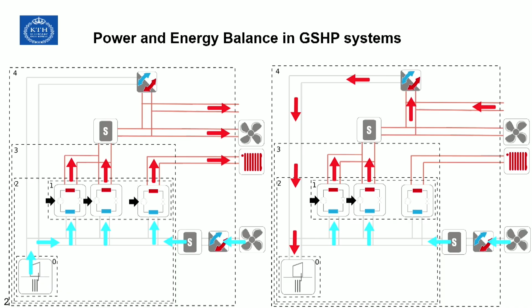This is the nice thing about heat pumps: we have an energy balance that's always there, both at an instant in time and over time. The three blocks at the bottom show blue plus black equals red: cold production plus electricity equals heat production. This balance lets us work with the COP for heating, which is the quotient between red and black, and for cooling, the quotient between blue and black.